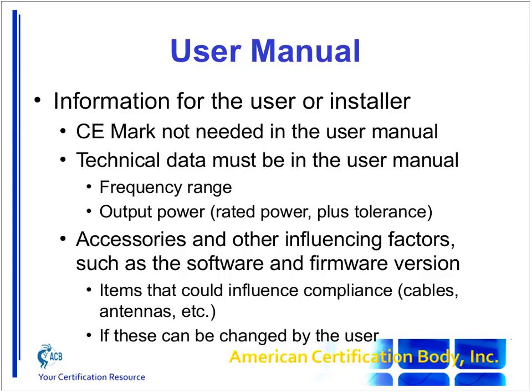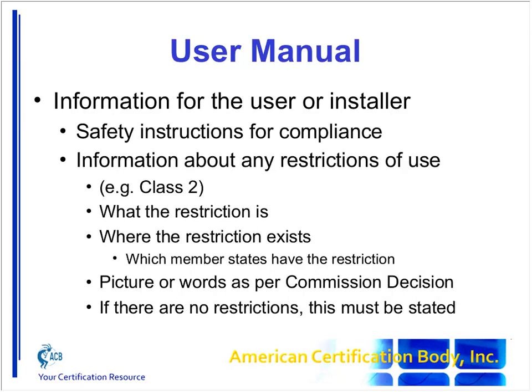The user manual must contain any safety instructions for compliance, anything that's going to ensure the product stays safe. Also, any information about restrictions of use for Class 2 devices, such as what the restriction is and where it exists. There's a draft document with a picture of a book with an exclamation mark in it and a table of countries, which is the latest guidance on how to label the restriction on the user manual and on the packaging. We'd always recommend you follow the latest guidance.